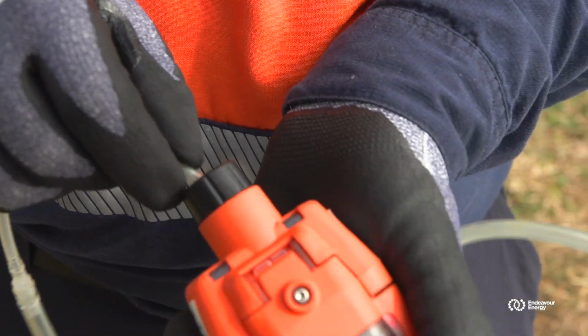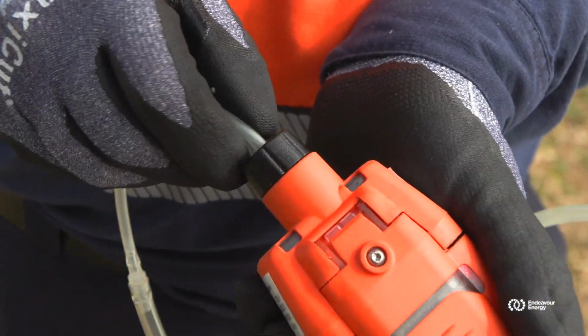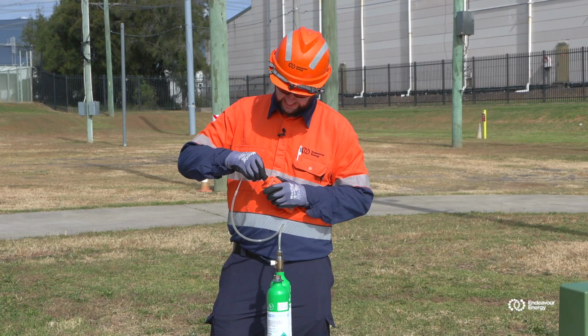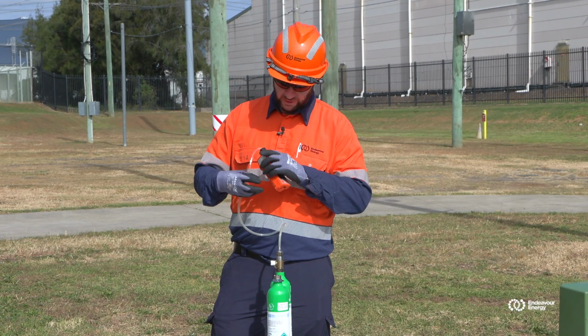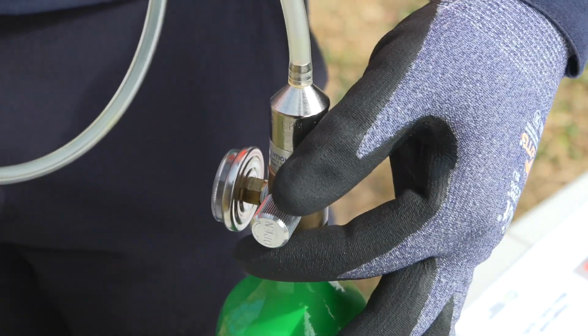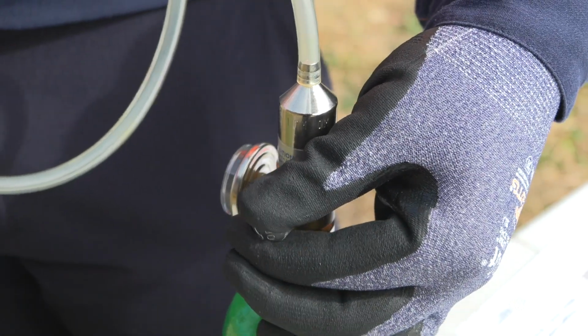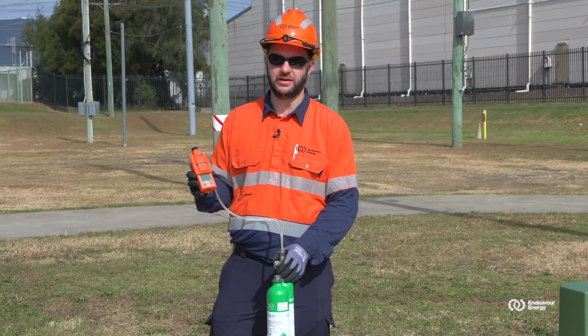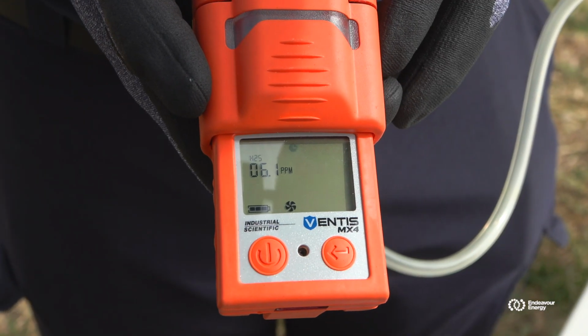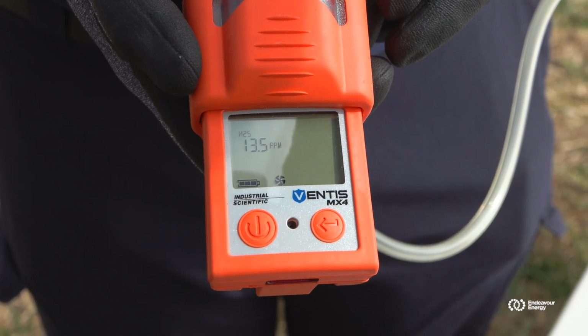And now we're going to connect the test gas cylinder hose to the top of the gas detector. Once connected, we open the valve on the regulator here, and we'll go through and test one of the four sensors at a time. Today, the first sensor which will be tested will be the hydrogen sulfide.